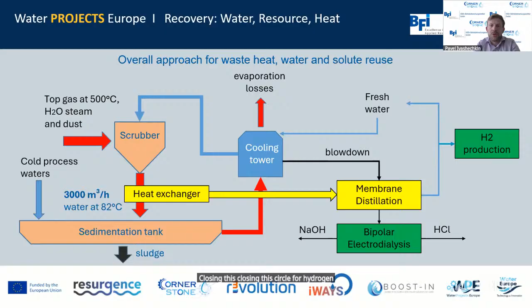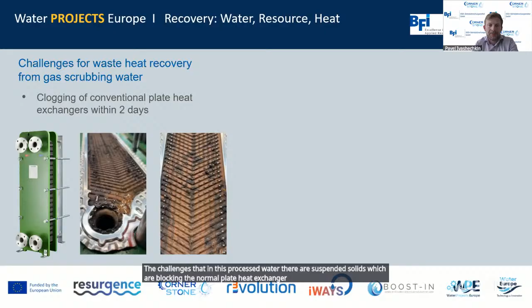The challenge is that in this process water there are suspended solids which block a normal plate heat exchanger within 2 days. So in the cornerstone project, we are developing a non-clogging heat exchanger that could look like this: a spot-welded heat exchanger with plates spaced 60 millimeters apart, instead of 5 millimeters as in a standard heat exchanger.